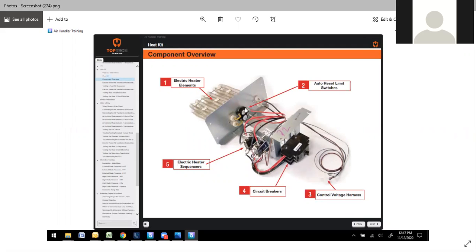You have your standard open air elements right here. You have your electrical sequencers right here. Depending on the number of elements that you have, that will dictate how many sequencers you have, as well as breakers. In this case here, you have basically 2 elements. You've got 2 safety limits here. Got your circuit breakers, and you have your control voltage with the 4-pin plug for your board. So you'll take this plug into your board.